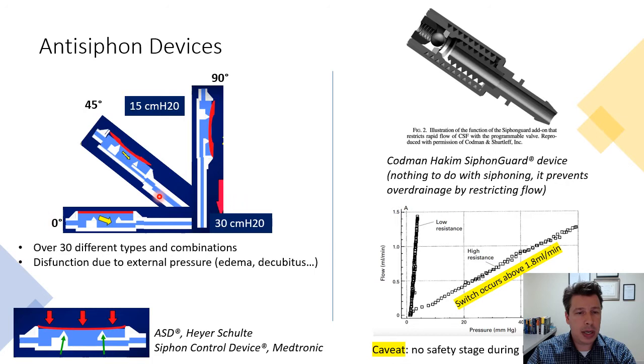This is where a certain type of device comes into play. When the patient moves from a lying to an upright position, the hydrostatic pressure itself pushes CSF downward, pulling a loose thin membrane against the inner surface of the shunt device, closing the passage for CSF. A drawback of these early systems was that surrounding tissues or external pressure could inadvertently close the system, causing a sort of malfunction. Modern anti-siphon devices on the market today avoid this complication.